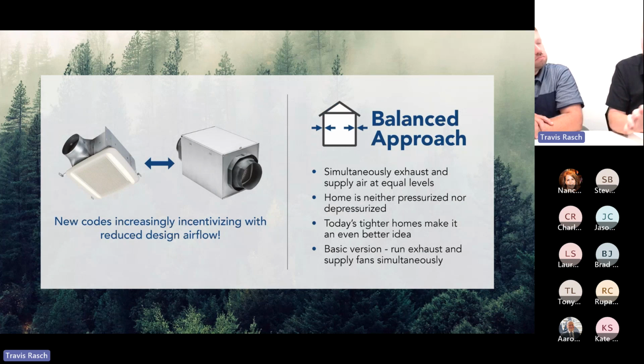So exhaust and supply are the two basic approaches. Depending what climate zone you're in, you may choose one or the other. But from here on, we're going to focus on balanced ventilation. The key is that energy efficient builders like you are building nice tight homes. The exhaust and supply approaches are counting on holes in a building envelope. If you're building tight, you don't have those holes. So you want to mechanically push bad air out and mechanically push fresh air in.